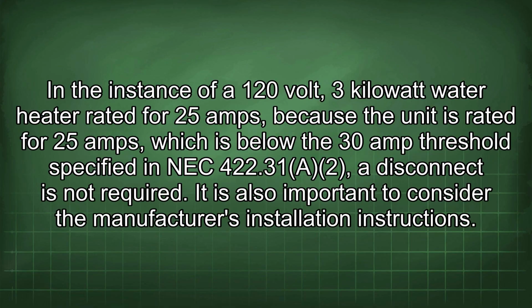In the instance of a 120-volt, 3 kilowatt water heater rated for 25 amps, because the unit is rated for 25 amps, which is below the 30 amp threshold specified in NEC 422.31(A)(2), a disconnect is not required.